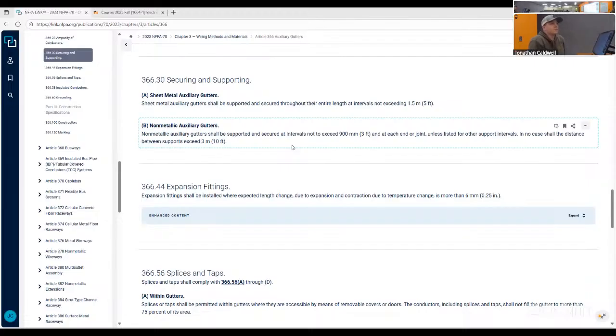For instance, at Sputnik, we had to do a double stack gutter below these panels because they wanted it all underground. One gutter was for feeders and one gutter was for just branch circuits. We ended up having to do metal support bracing from the floor to support these gutters. These gutters were probably maybe 12 inches from the floor, so it wasn't that much, but we still had to do that support. We also had to do reinforcing steel inside the gutters, just because there was so much weight from the feeders in there. Yeah, this was a lot. That service for the new building was almost 4,000 amps. So just think about 4,000 amps distributed into a bunch of different panels. It was a lot.